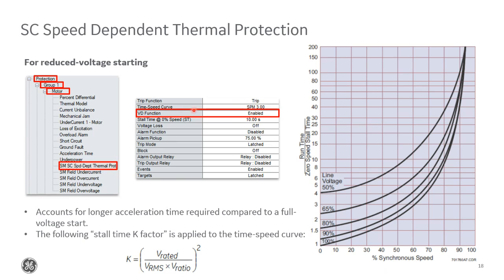In here, there's also a setting for voltage dependent function that can be enabled or disabled. Many motors involve reduced voltage starting. So in this scenario, the acceleration torque is reduced compared to a full voltage start, which means it takes longer for the motor to accelerate, but there's also less inrush current, so the heating rate is reduced. So when we enable this VD function option, the 869 is allowed to take advantage of the motor's extended stall time so that it can accelerate to full speed over a longer period of time without tripping.